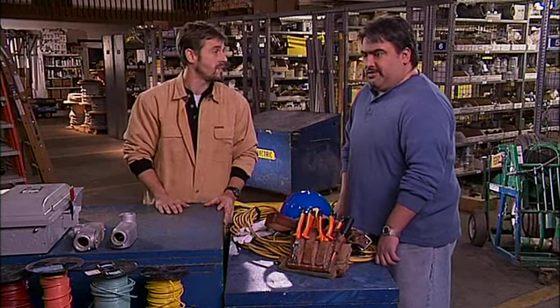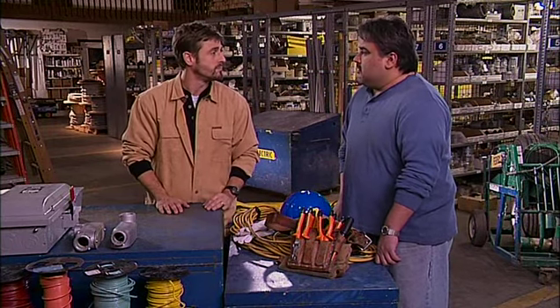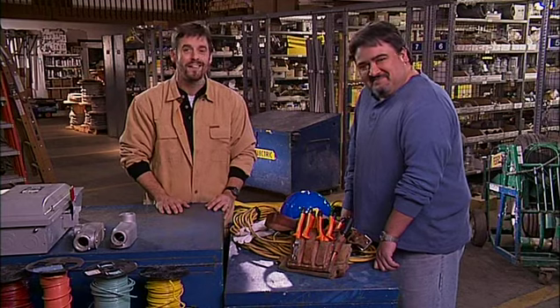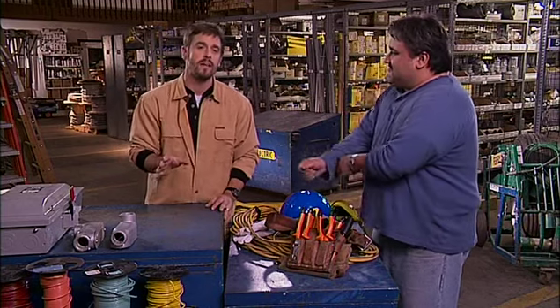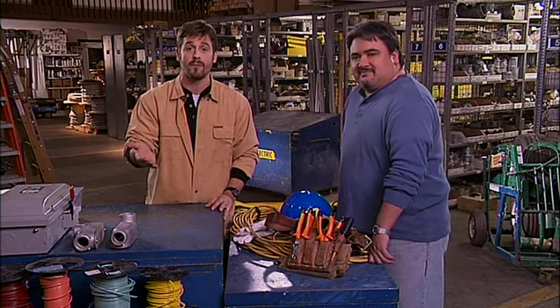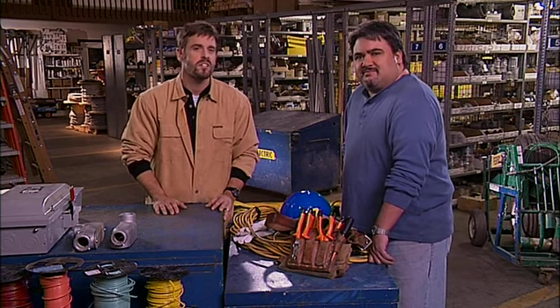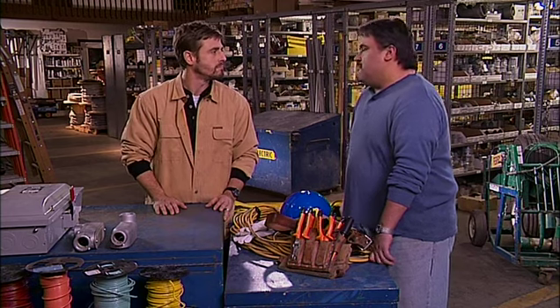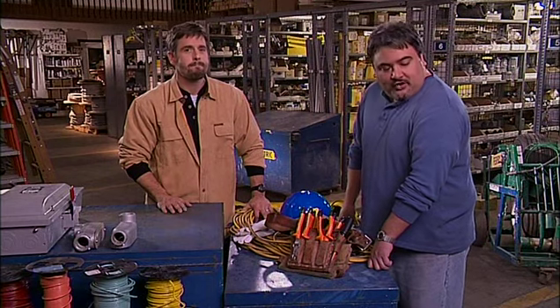You know, you can find out a lot of this information in the IEC standard. The IEC. Oh, the 61010-1, the International Standard for Test Equipment Safety? That's right. Now, you should select a meter with a safety rating that exceeds requirements for both the category and the voltage. For most industrial work, 600 volt Cat 3 will be the minimum acceptable. Max had a brand new meter, 1000 volt category 3 and 600 volt category 4. Really? So why was he borrowing one from you? Oh, he lent it out to somebody and they never returned it.